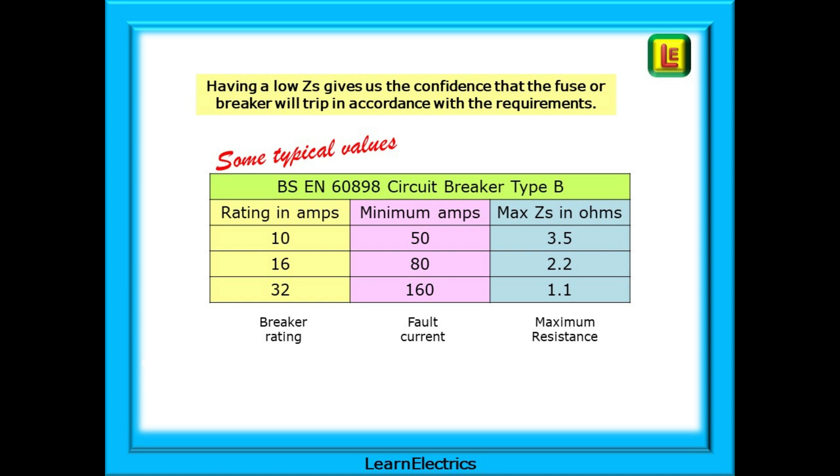Here, we've just chosen three different Type-B breakers to show the different amounts of fault current required to make them trip as required. Notice that the smaller the breaker rating, the bigger the ZS that is allowed. Smaller breaker sizes have a bigger allowable ZS for the circuit.